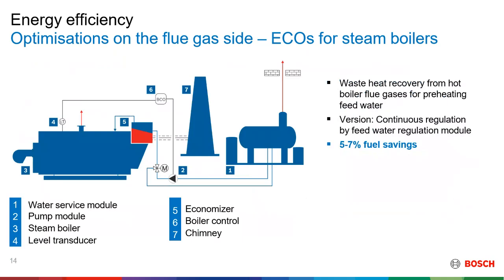So on this setup, as you can see, there's a slight difference from the previous slide. Here is a setup with the on-off pumps and modulating three-way valve. So water will leave the feedwater tank, flowing to the modulating three-way valve from the pumps. So the three-way valve will actually detect the amount of water that is flowing into the boiler. Okay, and with this modulating three-way valve, you can actually control the amount of water flowing into the boiler through the economizer with on-off pumps. Okay, next slide.